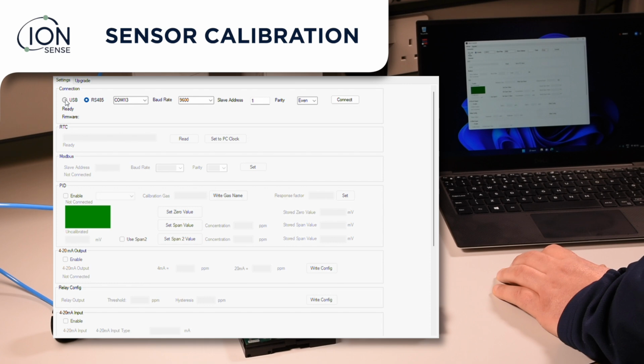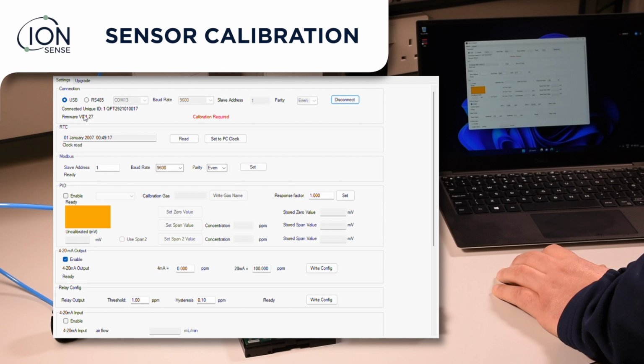Once set up and ready, select USB communication in the SDK software. And press Connect. Check your firmware is up to date. You'll see that a calibration is required. The date and time on the control board can be set manually, however, in this case, it's set to match the computer. Modbus settings will be left as they are unrelated to the USB settings. When Enable is pressed, power is supplied to the MiniPID sensor and a reading in millivolts from its output can be seen. Select the MiniPID you are using from the drop-down list. The software will prompt you to run a calibration, just click OK.